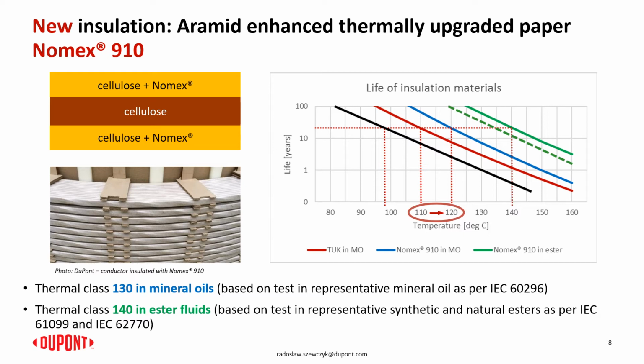So when we tested the material in mineral oil as compared to the thermally upgraded paper, we could observe that the normal operating temperature could be not 110 degrees Celsius like it is for the classic thermally upgraded paper, but it could be 10 degrees higher. It could be 120 degrees. In esters, that could be even higher. So in esters, we could get to the normal operating temperatures between 130 and 140 degrees Celsius in the extreme case. So this paper provides the improvement compared to the thermally upgraded paper, and it might be in the ester liquids, but even in mineral oil, it already offers the improvement of the thermal performance and the life of the insulation system.